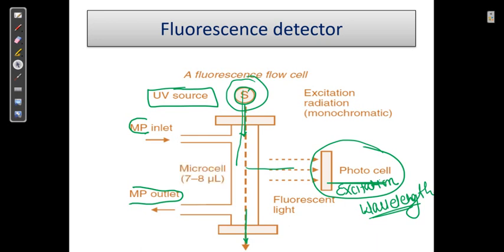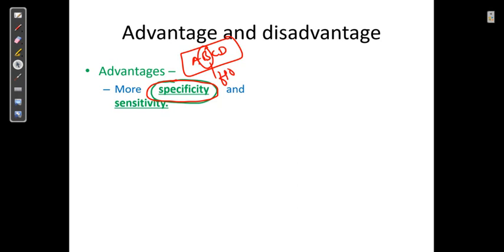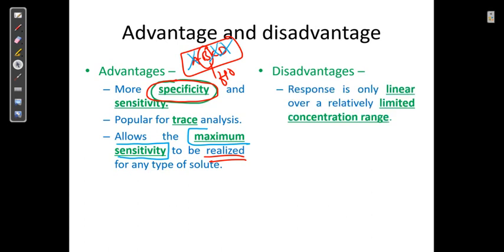The fluorescence detector is more specific. Its advantage is that it detects only specific compounds — for example, from a mixture of A, B, C, and D, only C (the fluorescent compound) will be detected. It is popular for trace analysis and allows maximum sensitivity to be realized for any type of solute.